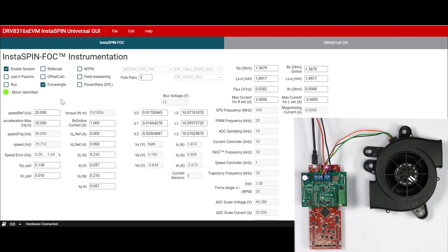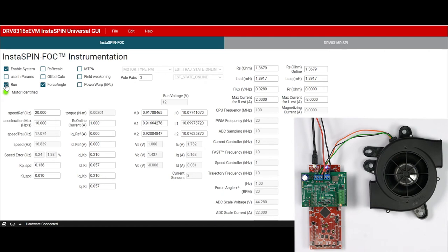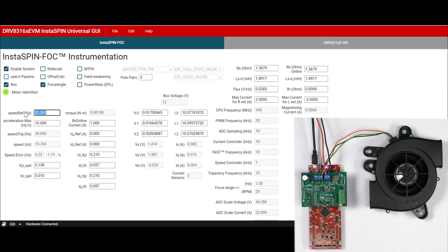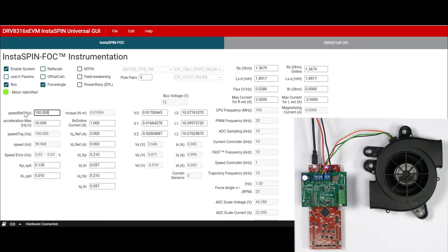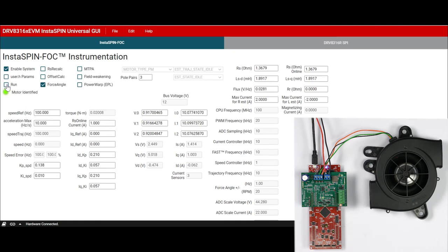Once the motor identification is complete, the motor identified LED will turn bright green. Click on Run again to spin the motor at the configured speed reference called Speed Ref. This input sets the electrical speed of the motor in hertz and will accelerate to that speed at a fixed acceleration. To stop the motor, simply uncheck the Run box and the motor will coast to a stop.